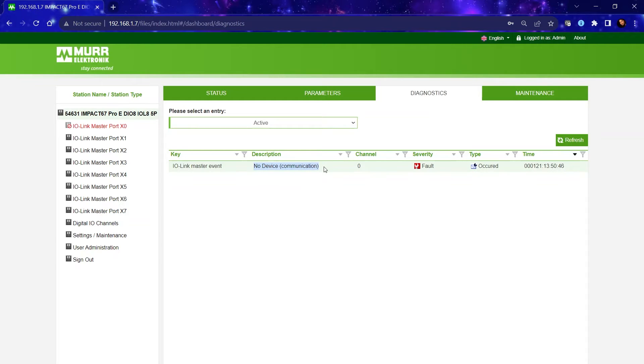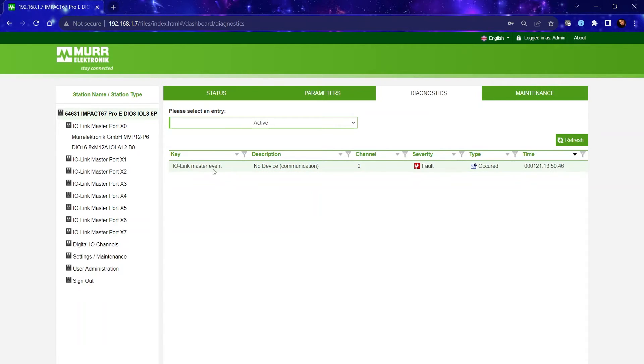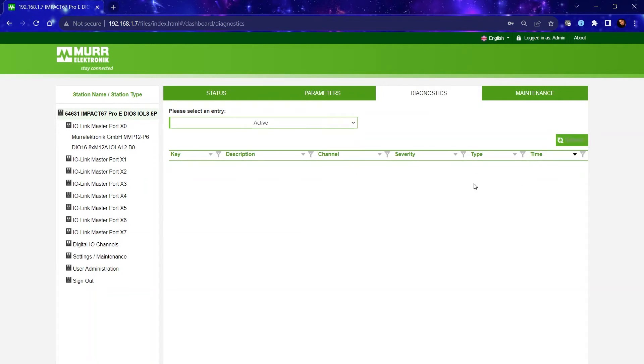So I'm going to correct the problem by connecting an IO-Link device to that port and you will see that it appears right here on the left-hand side. And once I do a refresh, the diagnostic message will disappear.